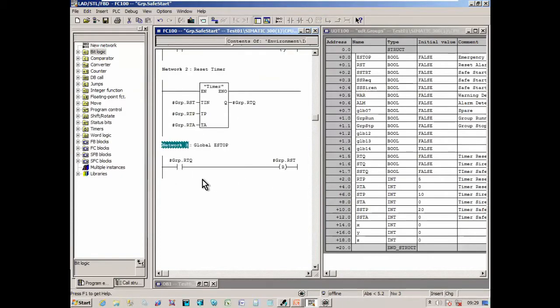Right, so now remember what we said, that is functionality you build into the SCADA that on area 1, you will have a button which says reset all the faults. That will put this bit on in this UDT, in this DB. It will then time out for the time, which is 5 seconds there, you can see. And then at the end, it will reset the same bit. So what that allows you to do, let's say you have interlocks which are also latched as a fault.